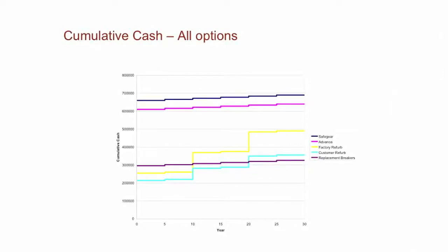And when you look at these, there's your options for your switchgear. Now these aren't your numbers; these are something that I had cut and pasted in there earlier. But for the sake of the exercise, what we've got here is you look at the arc-resistant gear: relatively low maintenance, low cost on refurbishment. You look at the old gear. The yellow line is the factory refurbishment, and you see the big blips there every 10 years to do the refurbishment, and so on down the line.